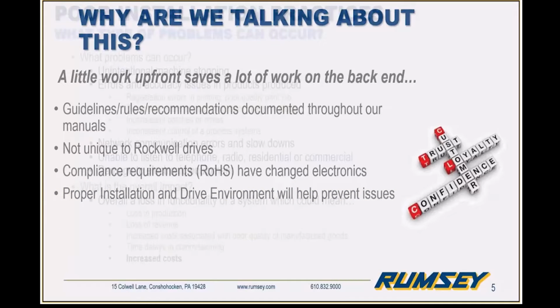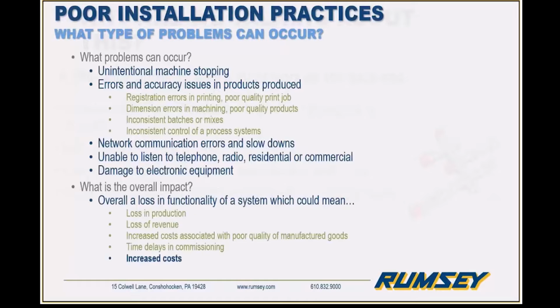So perhaps some of these issues look familiar. You may have seen them in your facilities where customers have these same issues. Basically, we could have problems arise as a fault on the drive itself, pretty straightforward, or improper installation can result in affecting other pieces of equipment external to the drive itself. If we take some time up front and look at the overall installation, we can eliminate a lot of these problems from occurring.